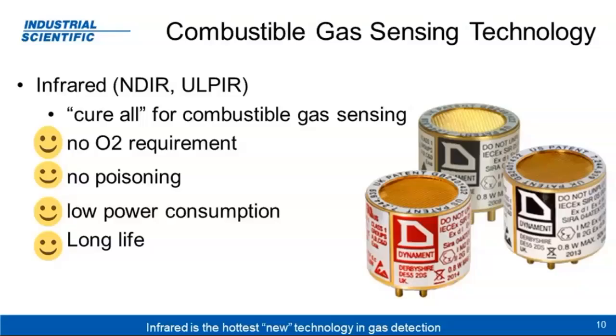Certainly applications for that, applications where the catalytic bead technology struggles. The infrared technology thrives there. There's no poisoning. You can't poison an infrared sensor, particularly in the case of the ultra-low power sensors. There is very, very low power consumption, so you're not eating batteries, not having to charge instruments every night, and you certainly get a long life out of these sensors, as there's no part of the sensor in particular, particularly LED-based infrared sensors, that has a consumable component. So the sensor's very long life.